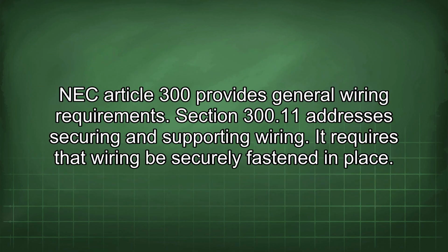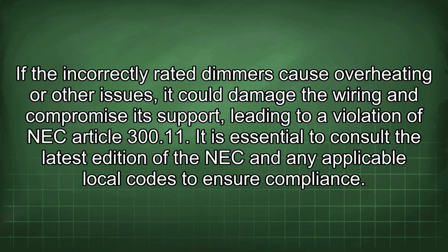NEC Article 300 provides general wiring requirements. Section 300.11 addresses securing and supporting wiring. It requires that wiring be securely fastened in place. If the incorrectly rated dimmers cause overheating or other issues, it could damage the wiring and compromise its support, leading to a violation of NEC Article 300.11.